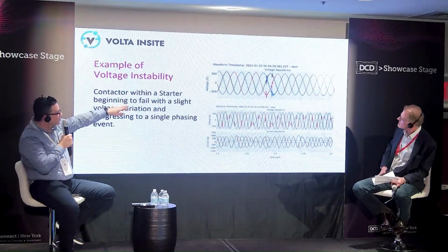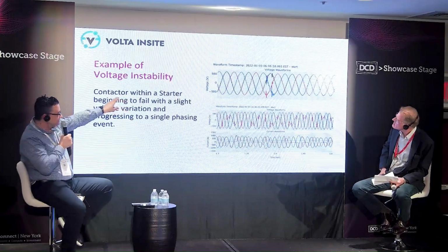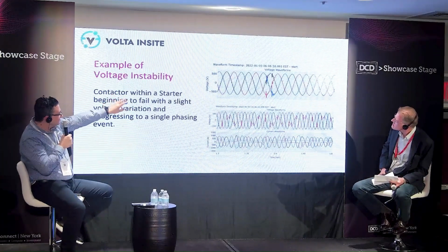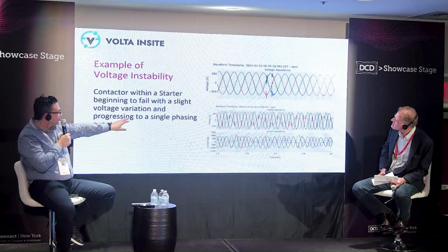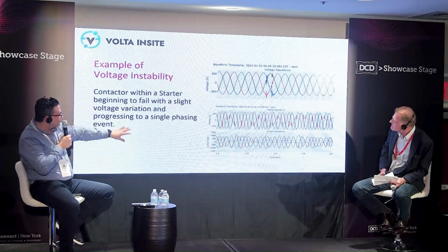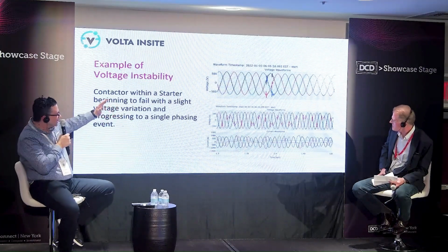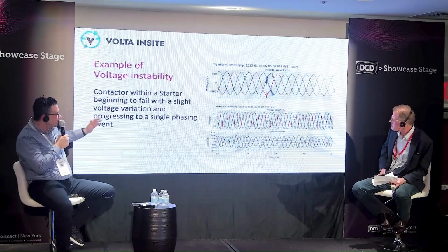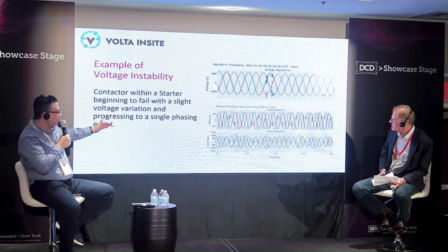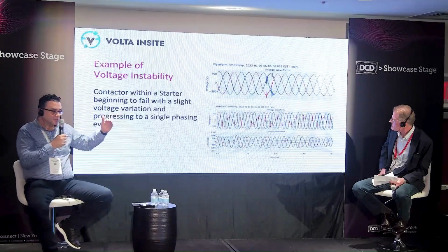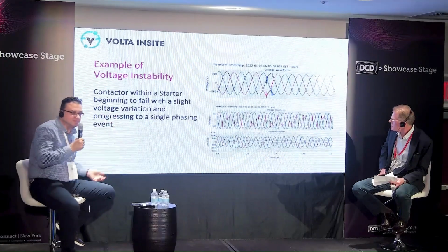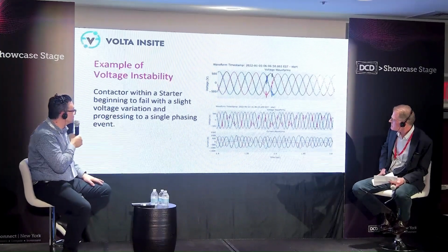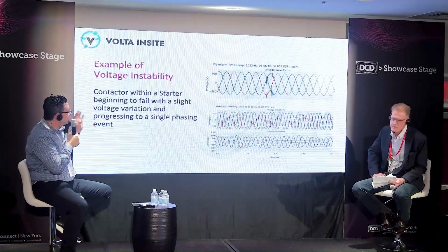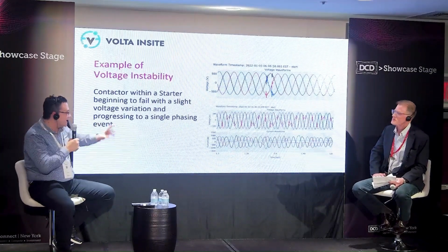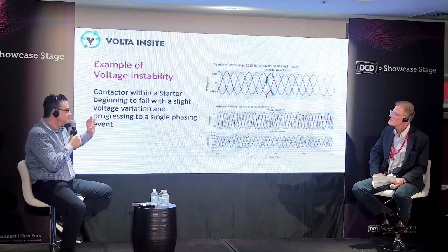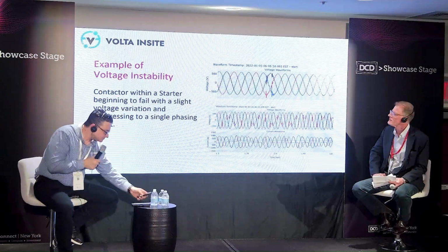Early in the morning, around 6 a.m., you'll notice the voltage variations happening very slightly. Then towards the end of the day at 4 p.m., you'll notice that contactor is losing one phase, and now you're single phasing your motor, which, if it's on a long enough cycle, will destroy that piece of equipment. That's the beauty of being able to capture these waveforms on a continuous basis.